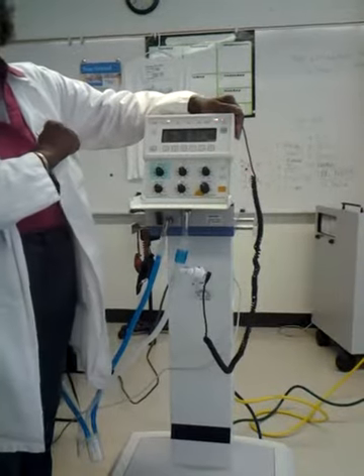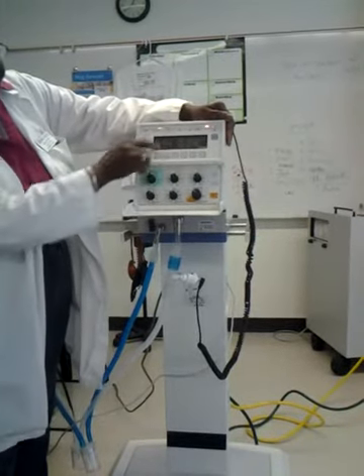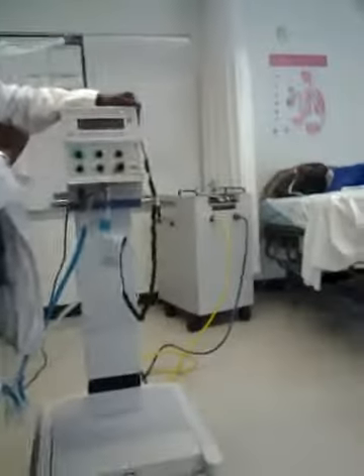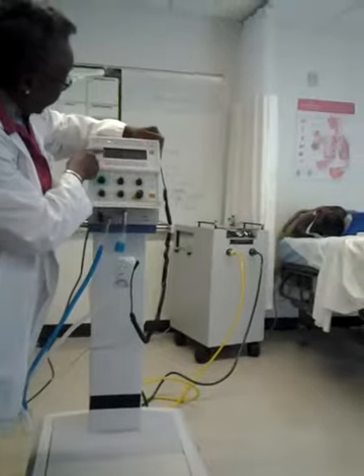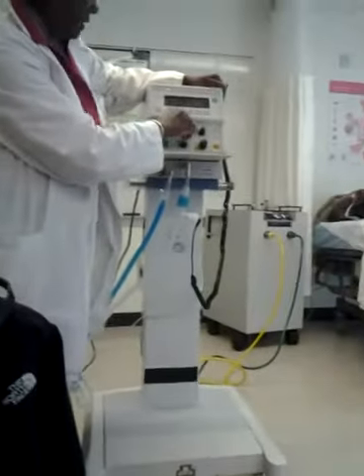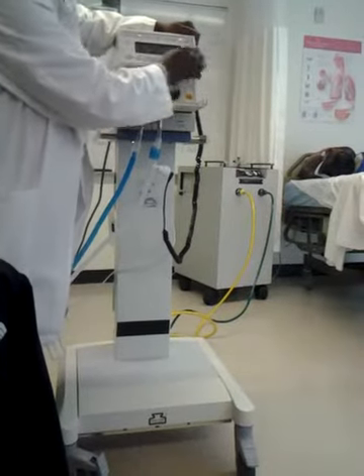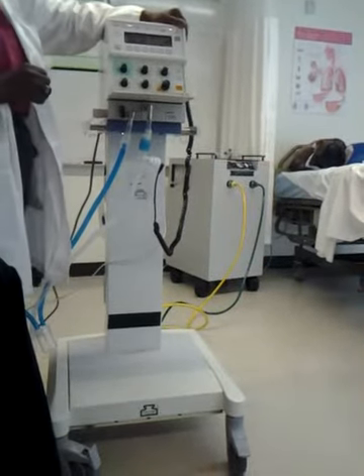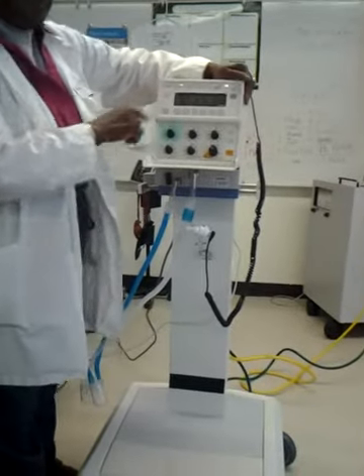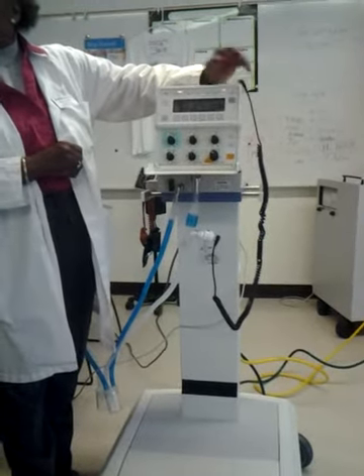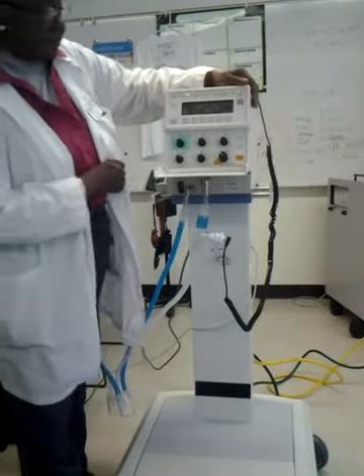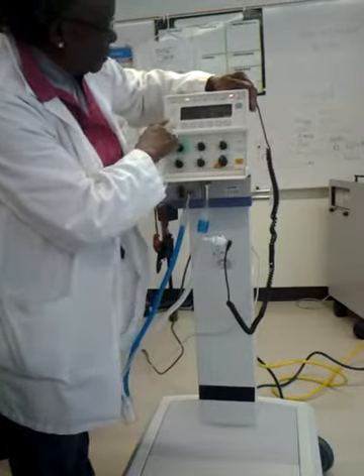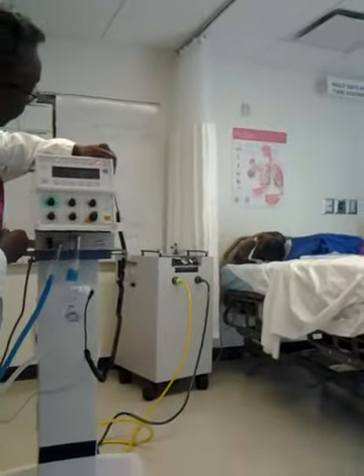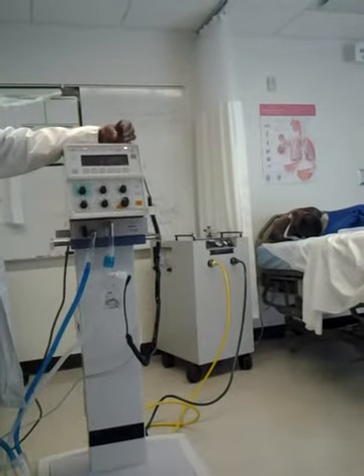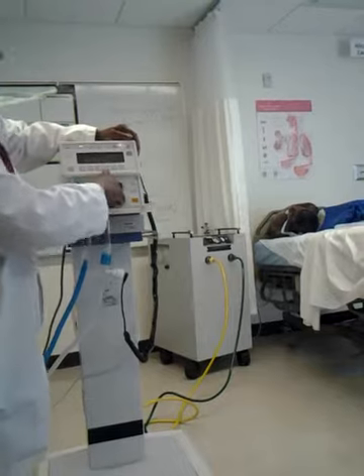And when you want to know your changes, you're going to hit list. Your changes are down here, but you want to read it on the screen to see what you're actually doing. So if I want to change my I time, and I'm in list, it will show me what my I time is, what my E time is, my IE ratio, my peak flow, and all of that will be shown on this one. And then measurement 2 is measuring all of my parameters. So when you do your vent check, you want to look at list as well as measurement 2. This is where it does a lot of your measurements for you. It's going to get your compliance, your resistance, your airway resistance. If we were going to do those measurements, you would go to measurement 2.